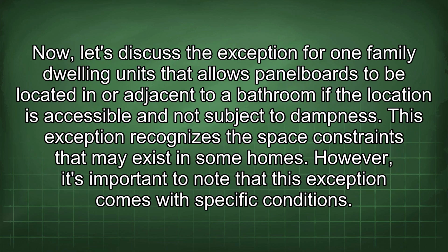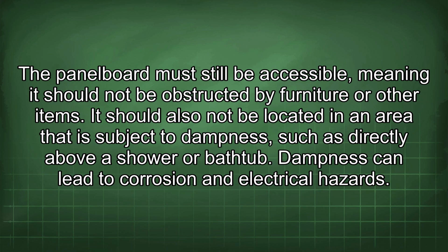Now, let's discuss the exception for one-family dwelling units that allows panel boards to be located in or adjacent to a bathroom if the location is accessible and not subject to dampness. This exception recognizes the space constraints that may exist in some homes. However, it's important to note that this exception comes with specific conditions. The panel board must still be accessible, meaning it should not be obstructed by furniture or other items.